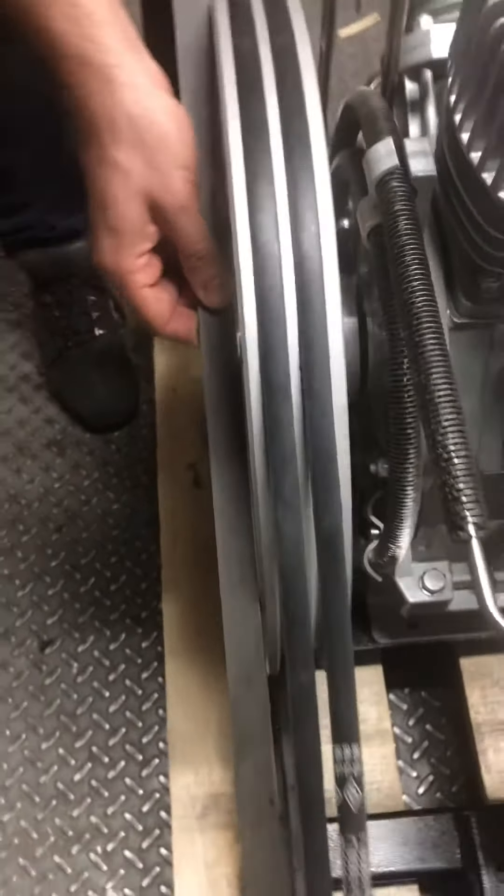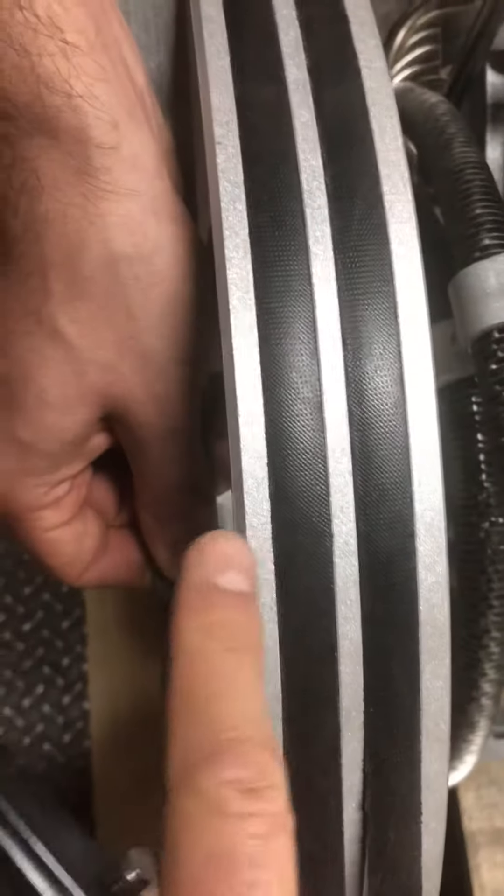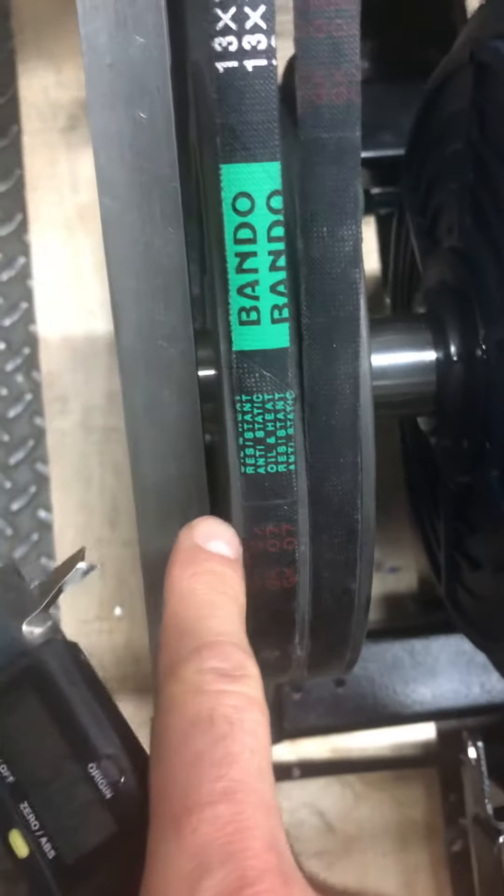There is the motor's pulley — you see they are not perfectly aligned because the thickness of the compressor's flywheel is larger than the thickness of the pulley. So you can use a tool like this to align them.